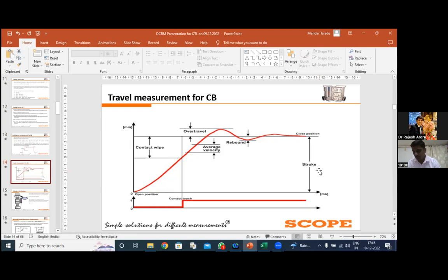I forgot to mention one point: in case of timing, it is a voltage test where we apply the voltage to one contact of the CB, one side of the CB, and we sense on the other side. So this is the voltage application method, where we apply the voltage and sense the potential at the second point of the switch. If the switch is in the closed condition, we get logic 0. If the switch is in the open condition, we get a logic 1 signal. With the help of this, we can calculate the timing and display it, and accordingly we get the different timing parameters like close, open, CO, OC, OCO.